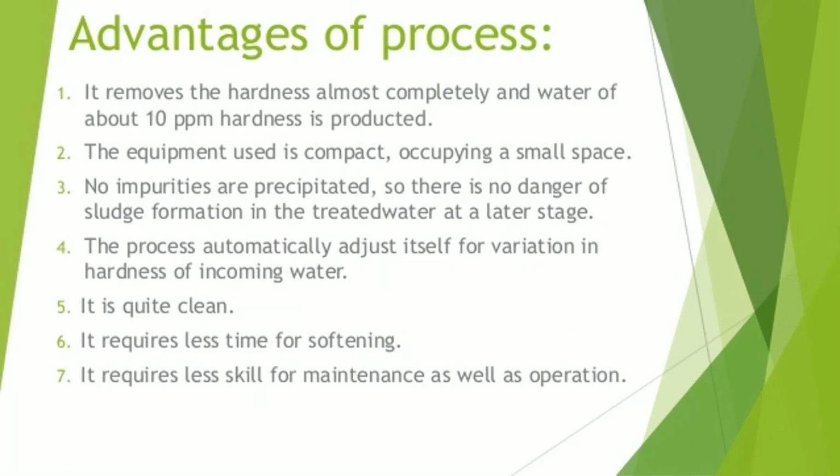Let us study the advantages of the zeolite process. The first advantage is that hardness is nearly completely removed and water of about 10 ppm hardness is produced. Second, the equipment used is compact and occupies less space. Third, impurities are not precipitated, so there is no danger of sludge formation.